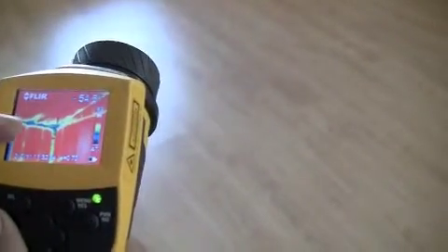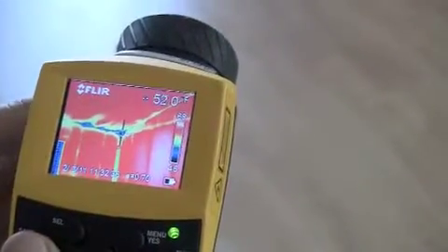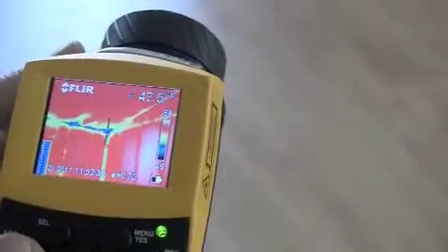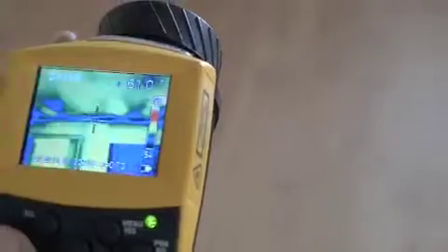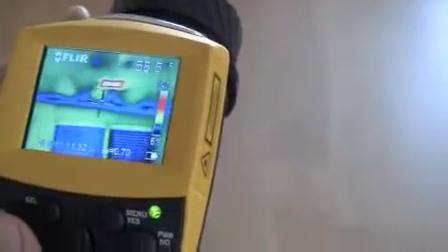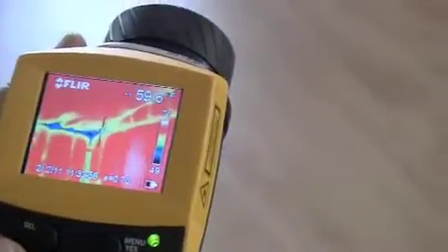Definitely, we can tell that it's 50-some degrees, and the set point temperature inside this home is 67. At the top corner of that wall there, we have major thermal bridging and basically no insulation. We can see that all across the top of the wall, the insulation was installed incorrectly. What can cause that?